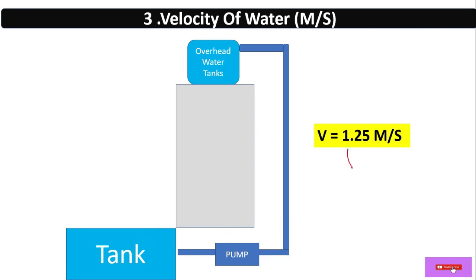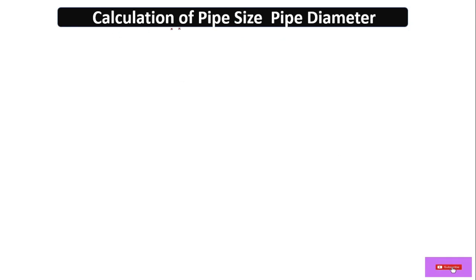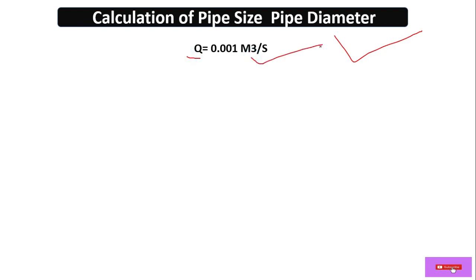In this case, we take V = 1.25 meters per second, which is the pressure velocity. Now in Step 4, we calculate the pipe size. We already have Q = 0.001 m³/s and V = 1.25 m/s.